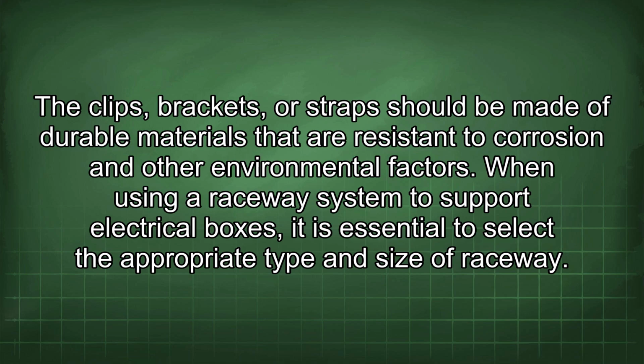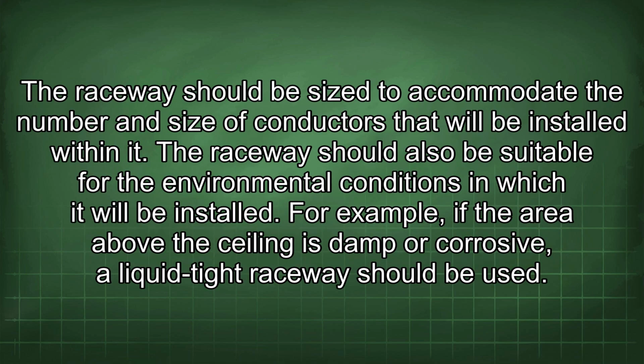other environmental factors. When using a raceway system to support electrical boxes, it is essential to select the appropriate type and size of raceway. The raceway should be sized to accommodate the number and size of conductors that will be installed within it. The raceway should also be suitable for the environmental conditions in which it will be installed. For example, if the area above the ceiling is damp or corrosive, a liquid-tight raceway should be used.